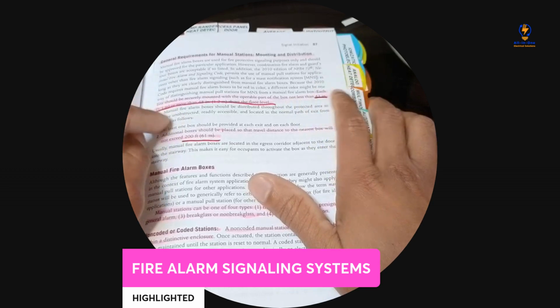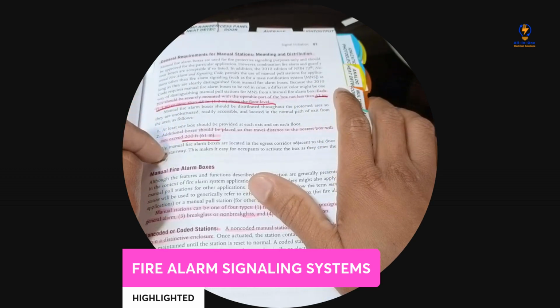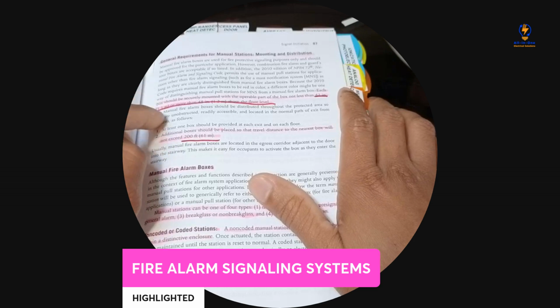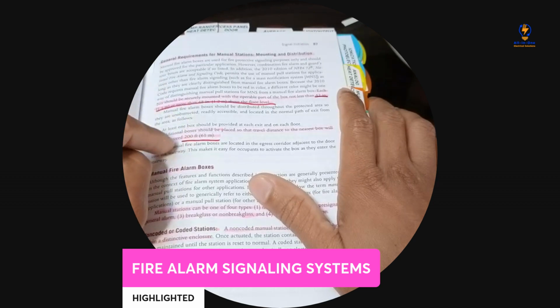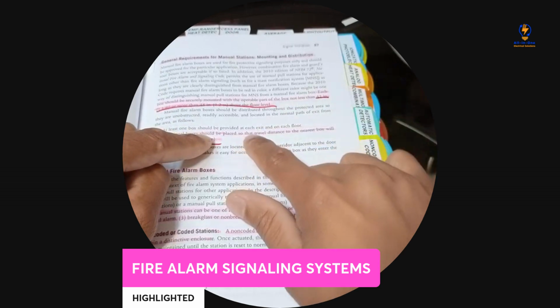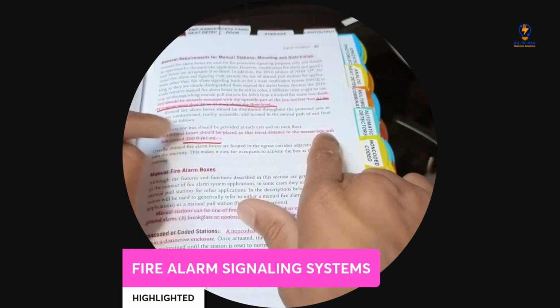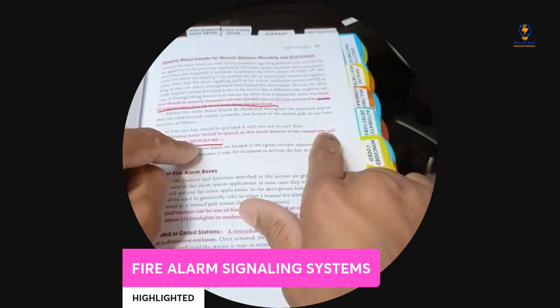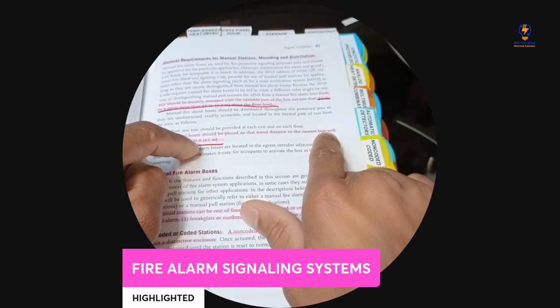Okay. Another gem right here. Another gem, guys, right here on the same page. You're going to go to the following paragraph and go to number two. Number two in this paragraph says additional boxes should be placed so that travel distance to the nearest box will not exceed what? 200 feet.